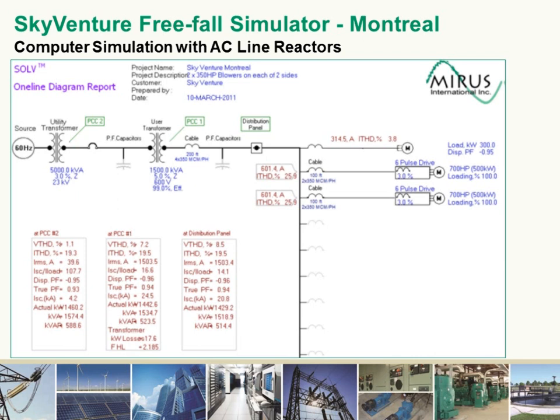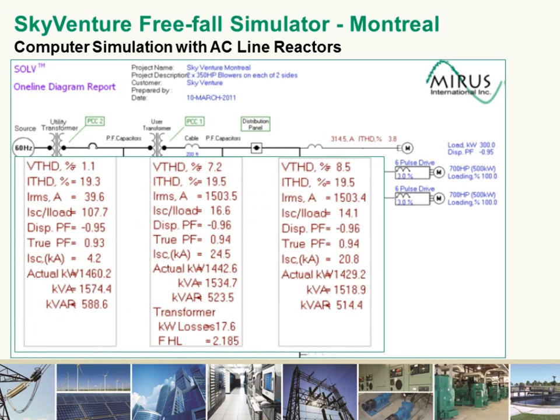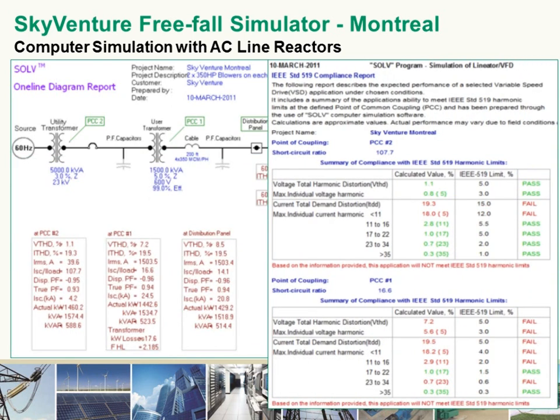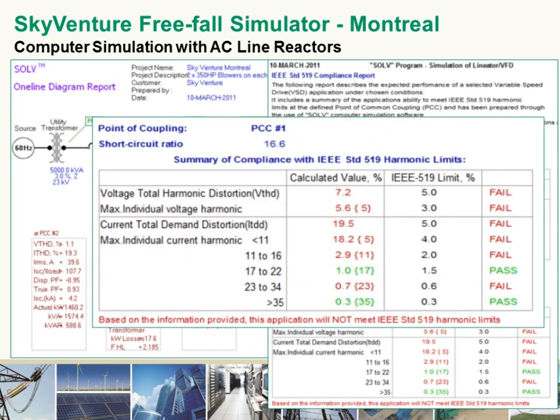We ran the simulation, and we can see that there were very high levels of voltage distortion and current distortion generated by the variable speed drives. When we look at the IEEE 519 compliance report that our computer simulation software will generate, we can see that the voltage distortion was well above 5%, and the maximum individual current or voltage harmonic was the fifth, and that exceeded the maximum level of 3. So we failed on voltage distortion. We also failed on current distortion in total demand distortion, and also with individual harmonics.